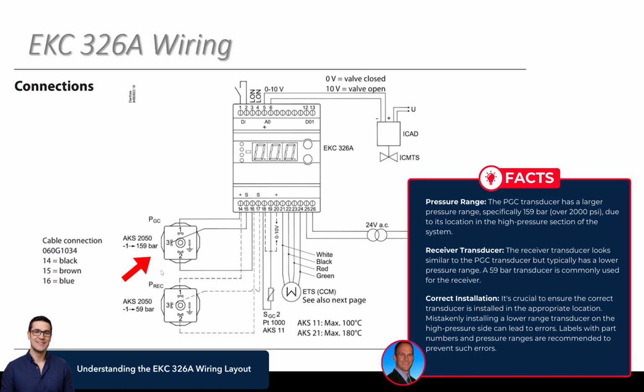They look very similar. As you'll see on the receiver transducer, the range doesn't have to be as high, and we typically use a 59 bar transducer there. But you do want to make sure that the right transducer is in place, because it's not too hard to accidentally install a 59 bar transducer on the high pressure side of the system where it needs to be reading 159 bar. So we put labels on the transducers with the part number and the pressure range and those types of things to help with that.